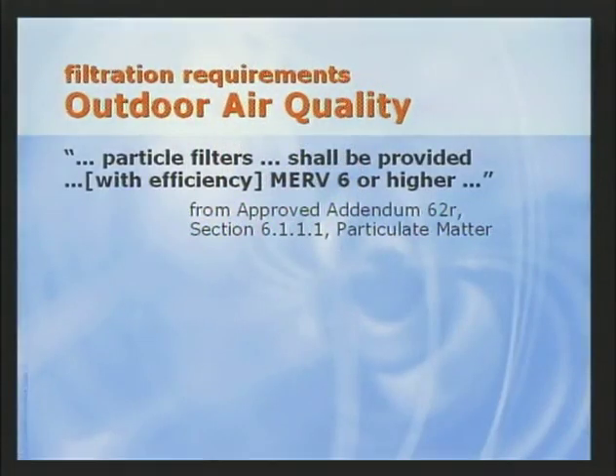ASHRAE Standard 62 now includes web-published addenda that better define and strengthen the outdoor air cleaning requirements. The designer is now directed by Addenda 62R to consider the outdoor air quality for particulate and chemical contaminants at the regional level for compliance with NAAQS, the National Ambient Air Quality Standard. Local air quality must also be based on an actual site survey. When particulate matter in the outdoor air exceeds the NAAQS limits, particle filters with an efficiency rating of at least MERV 6 must be used to filter the outdoor air.